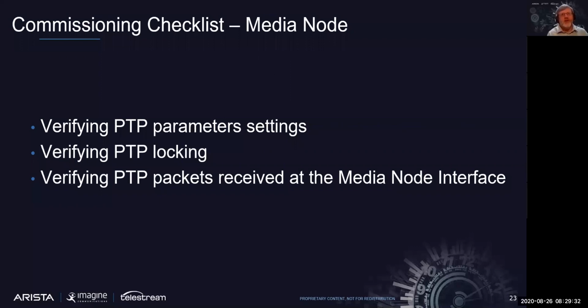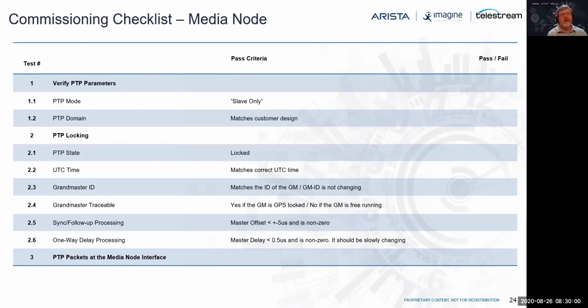For the media nodes, what you're going to be focusing on are parameters around, is it locking correctly? So you'll be checking your parameters and verifying, is it locking? Is it locking correctly? Because, for instance, if you're missing the delay request and delay response messages, your one-way delay calculation would be wrong. You'd still be locked, but your time might be shifted. So you need to get into that low-level detail. And you're looking at, for the most part, the devices coming into the media node. Again, this is part of a checklist.